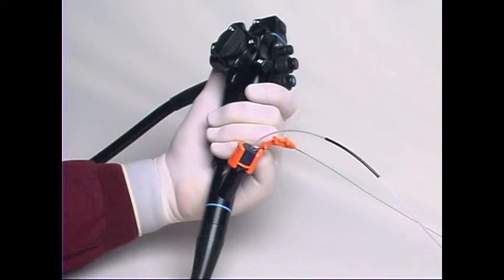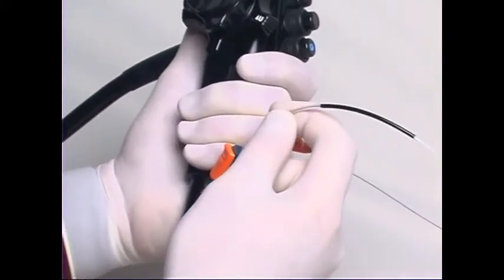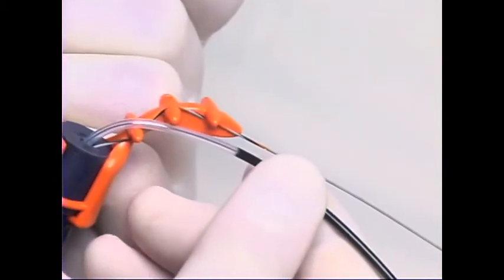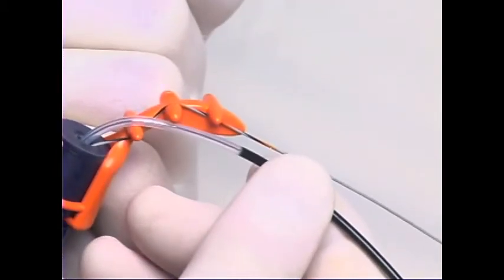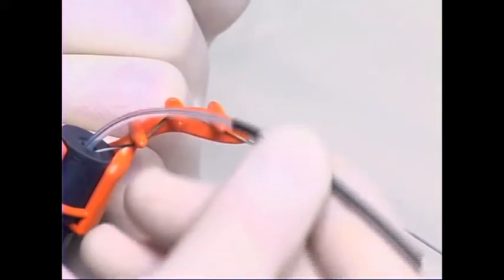The device IDE is used when it is critical that the position of the wire guide be maintained. With the wire guide locked in position, advance the device in order to perform an intraductal exchange. Advance the catheter until the distal end of the catheter IDE reference mark is aligned with the IDE reference mark on the wire guide. Continue to advance the catheter until the IDE reference mark on the wire guide reaches the proximal end of the catheter IDE reference mark. This is a visual indication that the wire guide is detached from the catheter and an intraductal exchange has occurred. The wire guide position has not changed. This can be verified fluoroscopically.